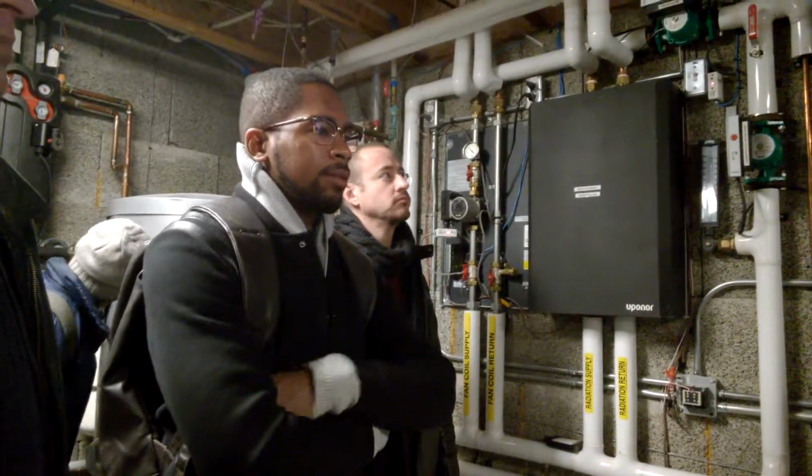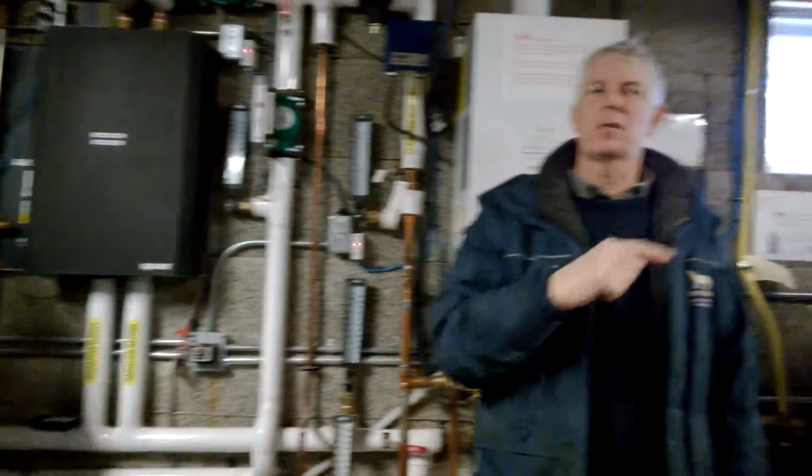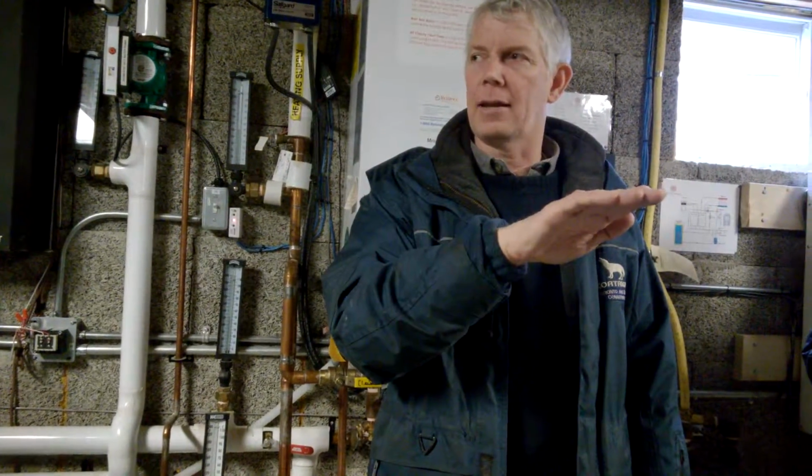I saw that you have a collector plate system. I was wondering if there's any solar absorption cooling system in the house or any chemical. Yes, we have in the house next door an absorption chiller that we can use with waste heat from the cogen. We're burning gas in a generator, and we can use the waste heat to heat the house, or we can use that waste heat through the absorption chiller, and it uses that heat to provide chilling.